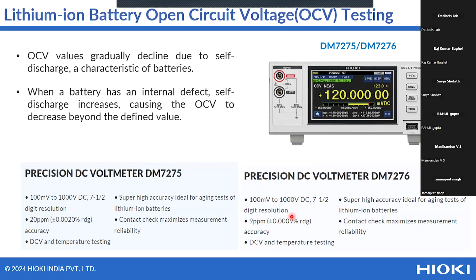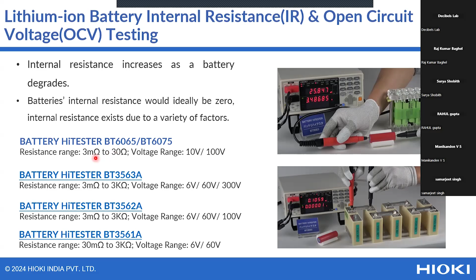And after that, lithium ion battery internal resistance means IR tester. You can use a number of testers, just like first one is BT3561, after that BT3562, after that 3563, and now recently 6065 and 6075. The range of this is 3 milliohm to 30 ohm. This is designed for battery testing, so you can get more stable and accurate results. The range of this BT battery tester is 10 volt to 100 volt. So up to 100 volt, you can directly test the resistance of the battery.